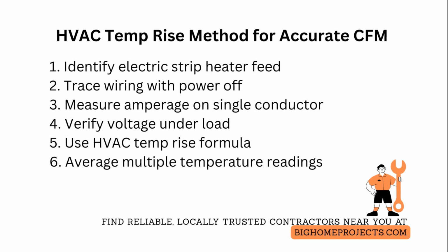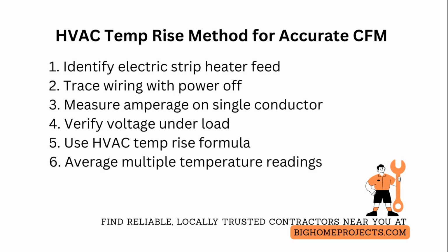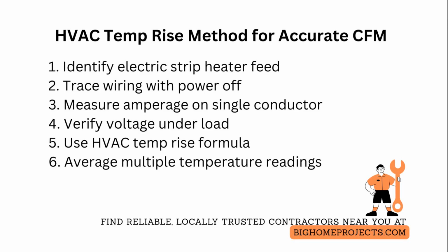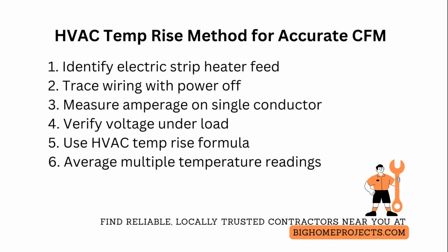When measuring, note that long extension cords, unbalanced phases, or loose connections create heat and voltage drop. Tighten connections and measure at the heater terminal for best accuracy.